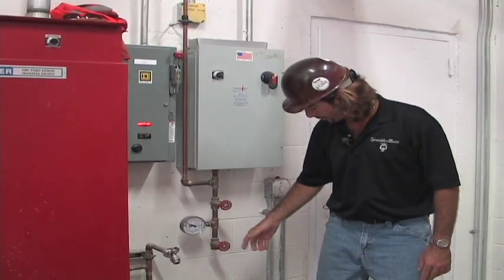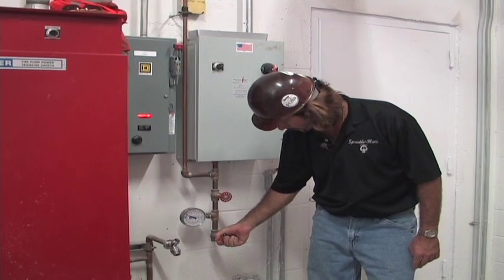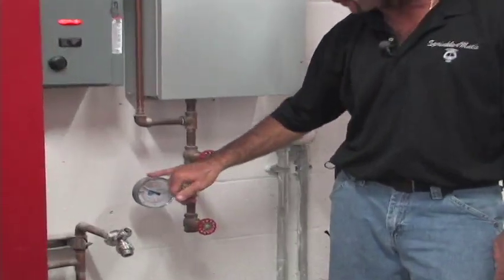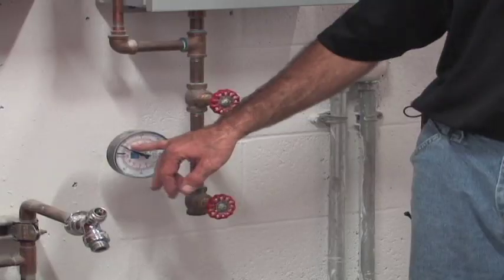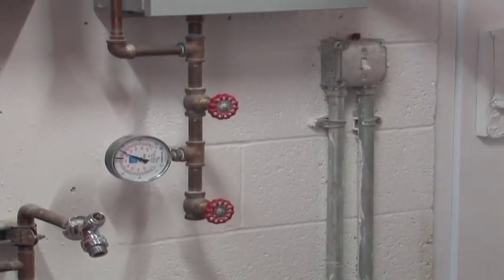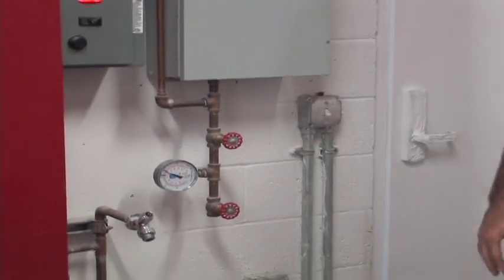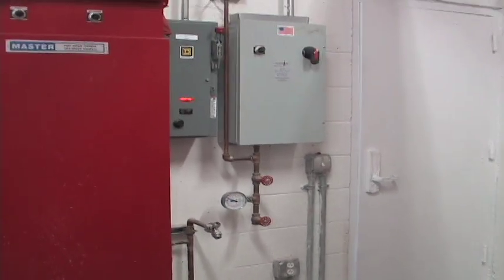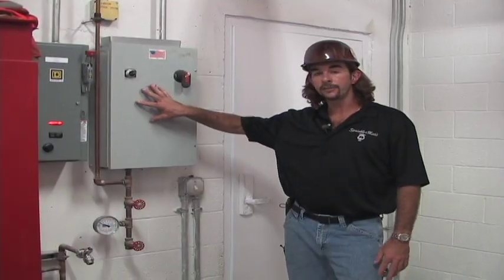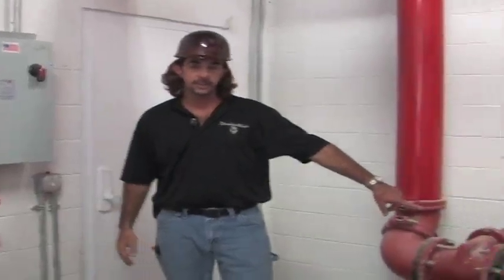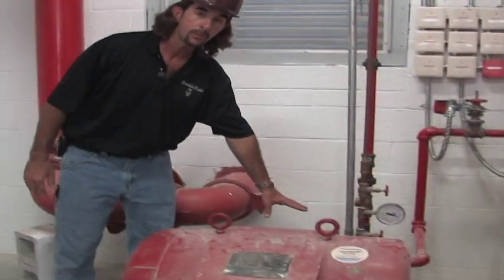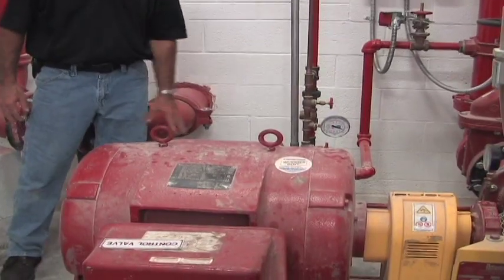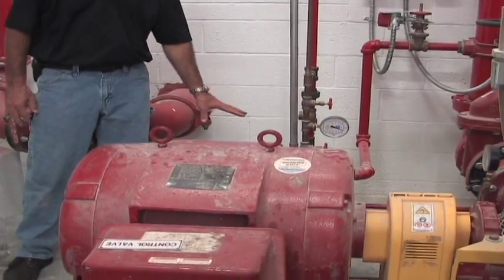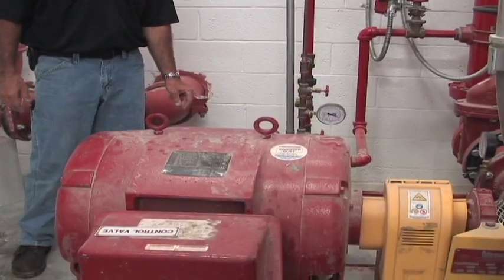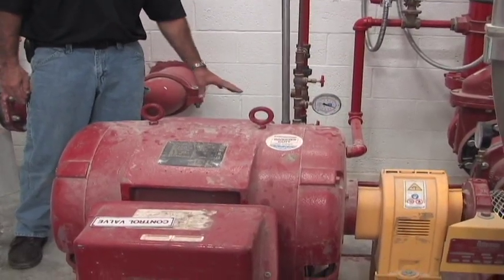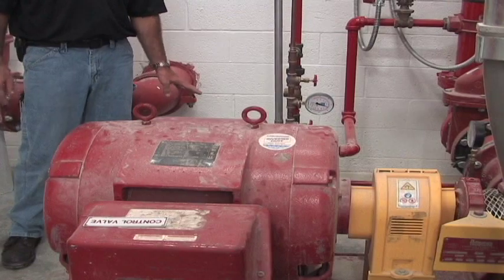Like I said, by turning this little valve right here, you'll hear it cycle on and cycle off from 160 to 180 psi. And like I said, this particular controller strictly just works our jockey pump. So this is our jockey pump controller, which is going to feed our one maintenance pump right here. The only purpose of this is to strictly stop the big pump, the main fire pump, from coming on. It's going to cycle from 160 to 180 automatically just with loss of pressure.